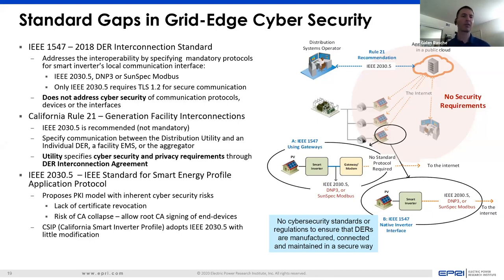If you're familiar with these protocols, you'll know that DNP3 and SunSpec Modbus do not have security built into them. It's only IEEE 2030.5 that actually requires secure communication. But even that IEEE standard itself doesn't directly address cybersecurity for the communication protocols or for the smart inverter interfaces, at least not in its current form.